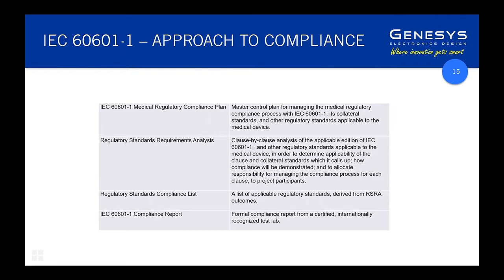For any project Genesys is involved with, we have formal 60601-1 assessments done by an accredited third-party laboratory such as TÜV in Singapore. Having the regulatory compliance plan in place at the start is good practice — it can be broadened to cover the other standards you're dealing with. The regulators will be convinced you know what you're doing. It's also absolutely critical to do a clause-by-clause analysis of 60601-1 at the start of your project so your team knows what it's facing.